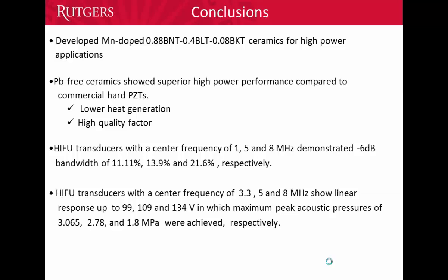We also measured the bandwidth for the HIFU transducers. It's 11.11, 13.9, and 21.6% respectively. And HIFU transducers with center frequencies of 3.3, 5 and 8 megahertz show a linear response up to 99, 109, and 130 volts, in which maximum peak acoustic pressures of 3, 2.78, and 1.8 megapascal were achieved.